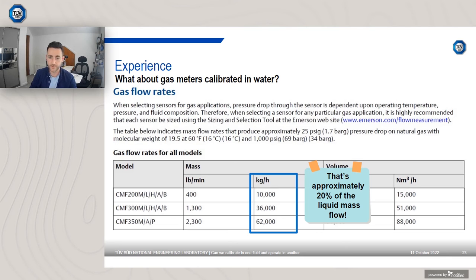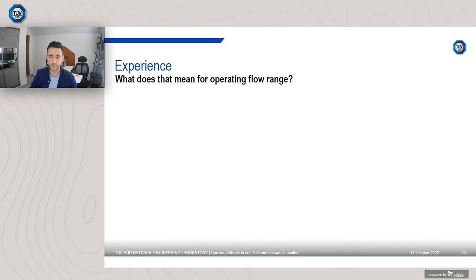Now, why is that an issue? Well, I'm not saying it is an issue, and it's not, because it's related back to your pressure drop for the Coriolis meter. That's how you ultimately specify your maximum flow. You can see it's detailed above there. I'm looking at a maximum pressure drop of 1.7 bar on natural gas at those conditions. Gives you your nominal mass flow rate. Also relates back to velocity in terms of how high a velocity you can achieve through your tubes, and then certainly with respect to your system and your overall pressure loss. So it is all related, and for gas, it's approximately 20% of the liquid mass flow.